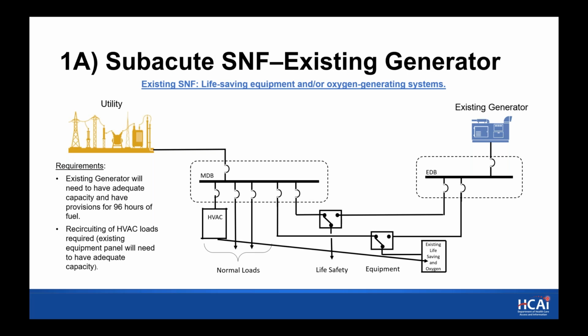with an existing generator. Again, now we're assuming that life-saving equipment and our oxygen generating systems are present, and that they're connected to the equipment branch. So very similarly, the scope of work to bring your facility within compliance of the bill could be to transfer your HVAC cooling equipment to the equipment branch, and then to take a look at your generator. Again, this is assuming your generator has capacity for the cooling loads, and then take a look at your fuel situation, and then bring that into compliance, or show that you do have compliance with the 96 hours of on-site fuel storage.